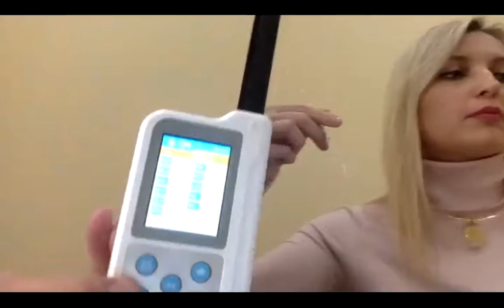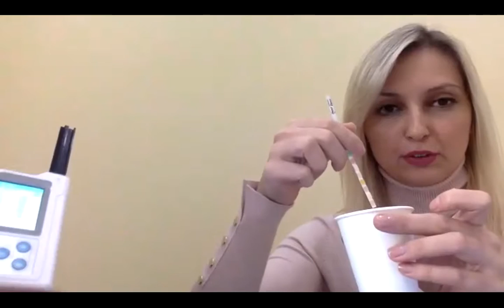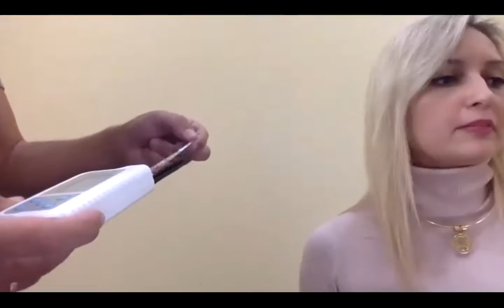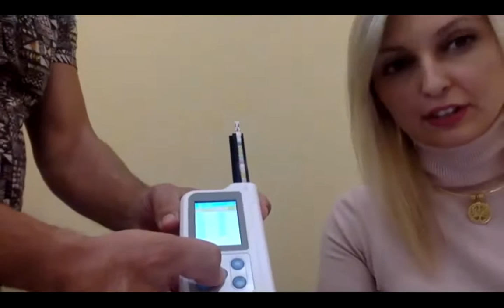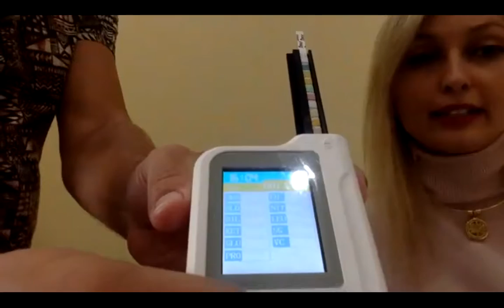Sergey, do we have on these strips already some liquid? Yes, Sergey has prepared it before, but in a normal situation, we take the urine, we put the strips inside, and after that, we put it in the device. After pressing OK, it starts the 60 seconds of waiting for the reaction on the test strips to start. And to make it more dry. Yes, and to make it more dry to get an efficient result in the Urine Analyzer. If you don't want to wait, we press OK the second time.